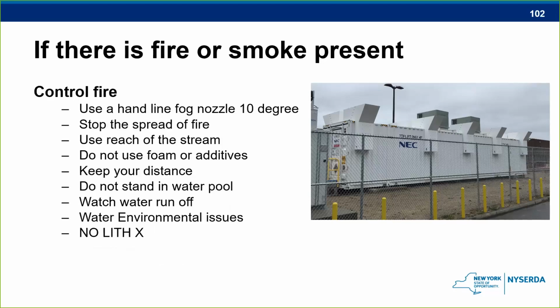Continuing on with the fire, if there is a fire, you can use a hand line, a fog nozzle at 10 degrees. The reason that we put that in there is because UL did some testing on it, right? We're not taught to put water on electrical components. And this is an electrical component. Not only is it electrical, it's electrochemical. And usually we don't use water in that situation. But we're telling you, you can use water in this situation.